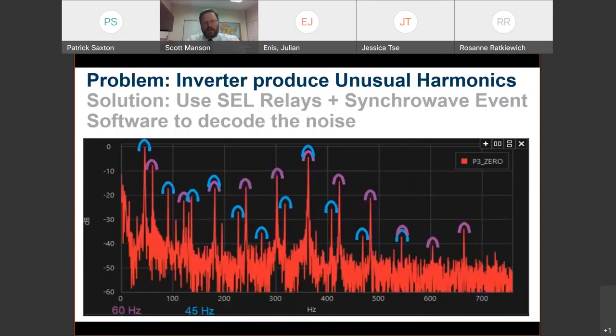Here's another example. As we know, inverters are driven by firmware, not by the physics of an air gap in a synchronous generator. As such, there's a lot of harmonic content that can be introduced to your grid by an inverter. And this has created problems, including transformer failures, cable failures, and worse. So the common question is, where are the harmonics coming from? How much content is there, and are they a problem? This is an interesting screenshot. This one's actually not an inverter. This one's a small backup generator in parallel to the grid that was producing enormous quantities of harmonics, problematic levels, like things were shaking on their mounts and causing inverters to tip over and shut off.